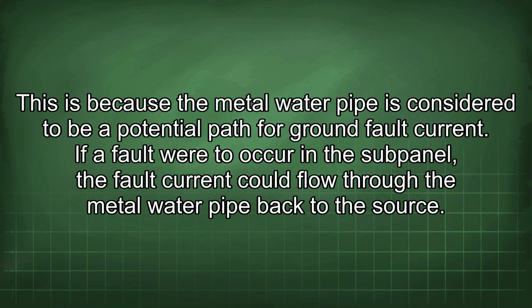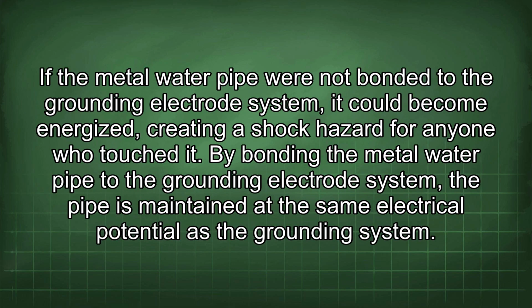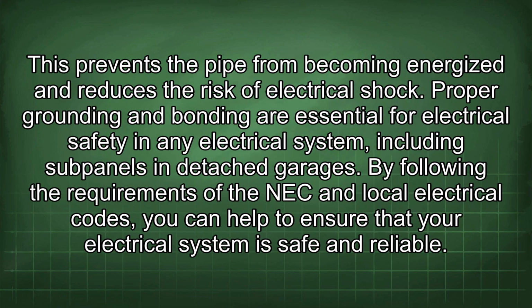If a fault were to occur in the subpanel, the fault current could flow through the metal water pipe back to the source. If the metal water pipe were not bonded to the grounding electrode system, it could become energized, creating a shock hazard for anyone who touched it. By bonding the metal water pipe to the grounding electrode system, the pipe is maintained at the same electrical potential as the grounding system. This prevents the pipe from becoming energized and reduces the risk of electrical shock.